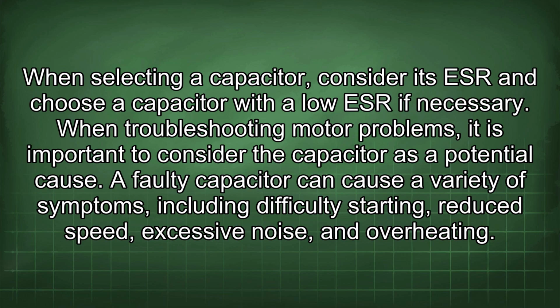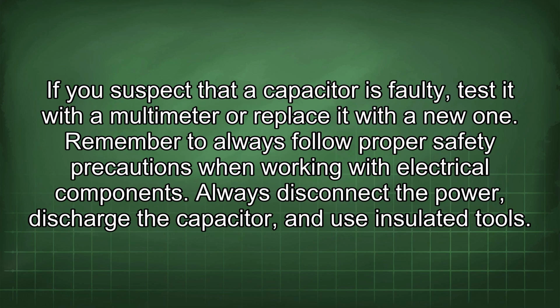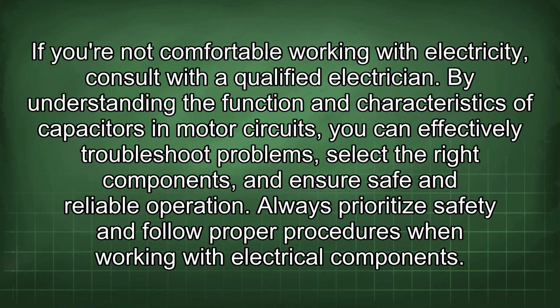When troubleshooting motor problems, it is important to consider the capacitor as a potential cause. A faulty capacitor can cause a variety of symptoms, including difficulty starting, reduced speed, excessive noise, and overheating. If you suspect that a capacitor is faulty, test it with a multimeter or replace it with a new one. Remember to always follow proper safety precautions when working with electrical components. Always disconnect the power, discharge the capacitor, and use insulated tools. If you're not comfortable working with electricity, consult with a qualified electrician.